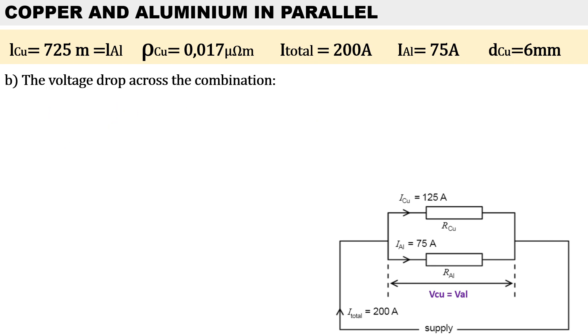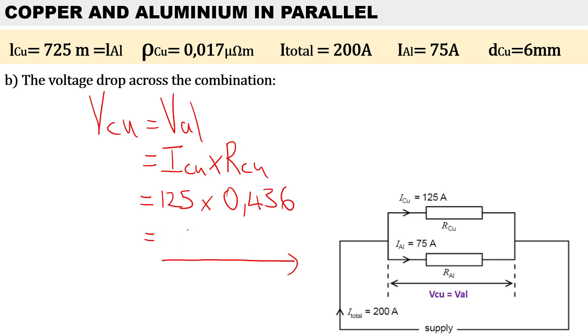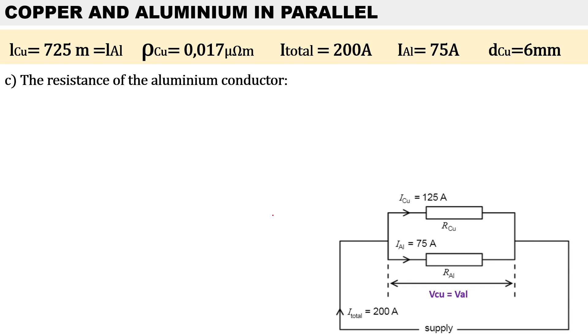For part b, calculate the volt drop across this combination. Voltage stays the same in parallel, so the voltage for copper will be the same as the voltage for aluminium. The current through the copper cable is 125 amps and the resistance for copper is 0.436 ohms. Therefore the volt drop across both conductors is 54.5 volts.